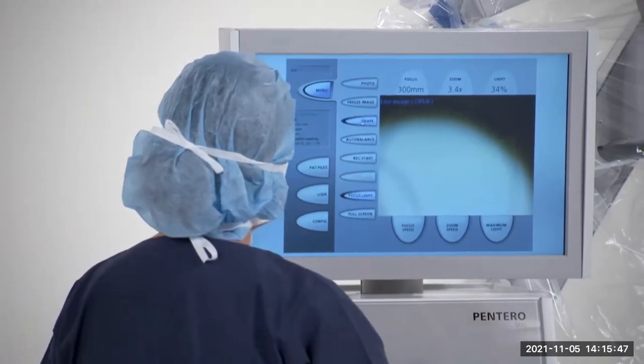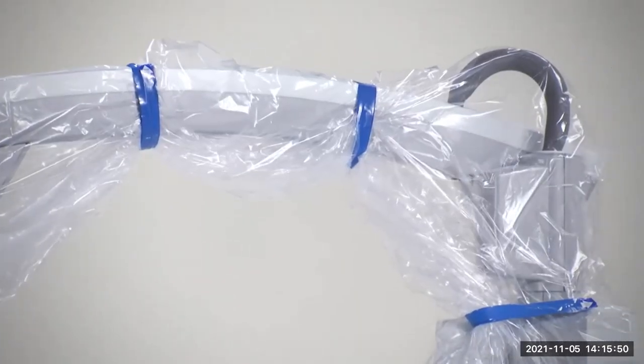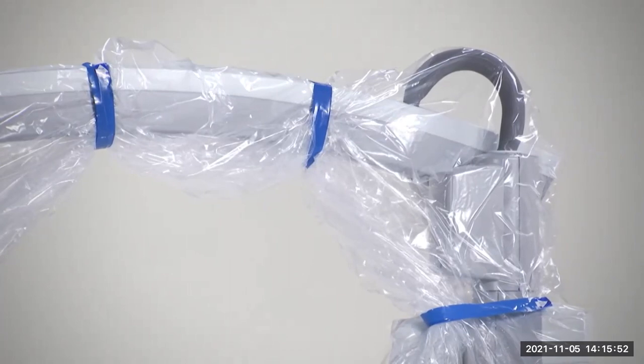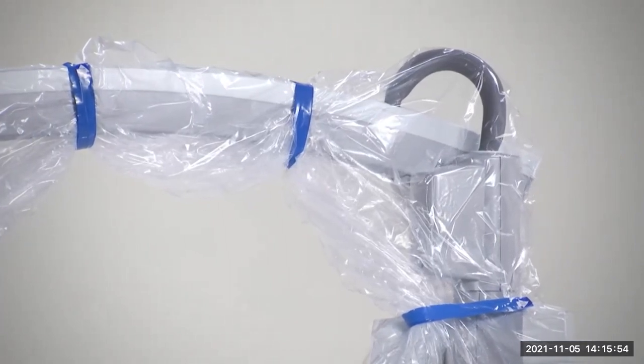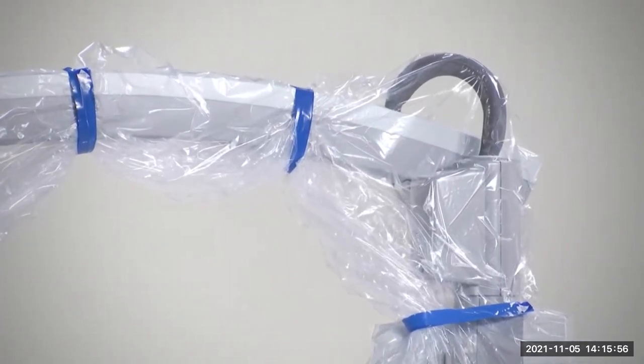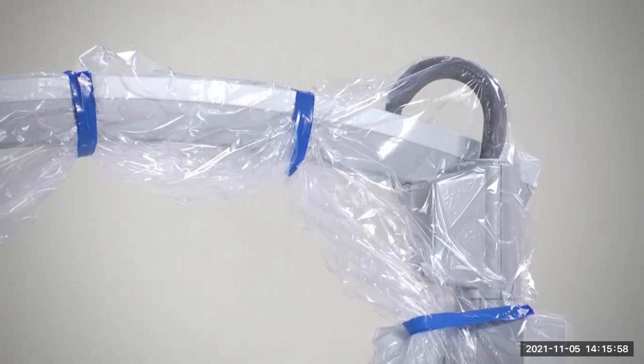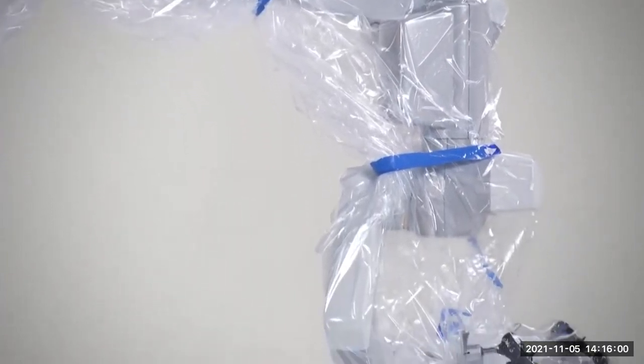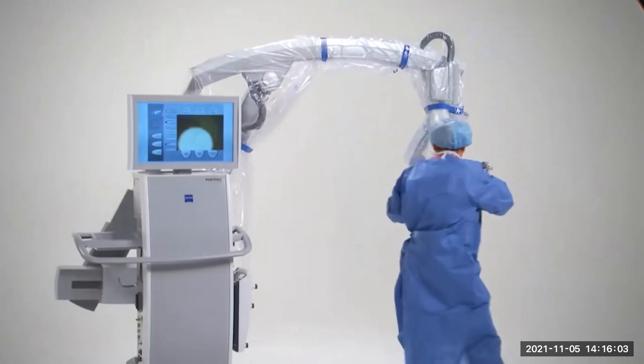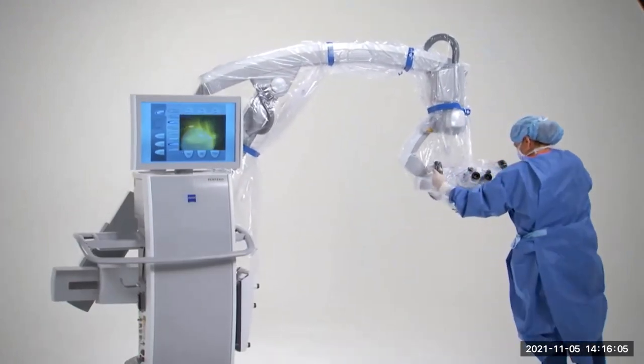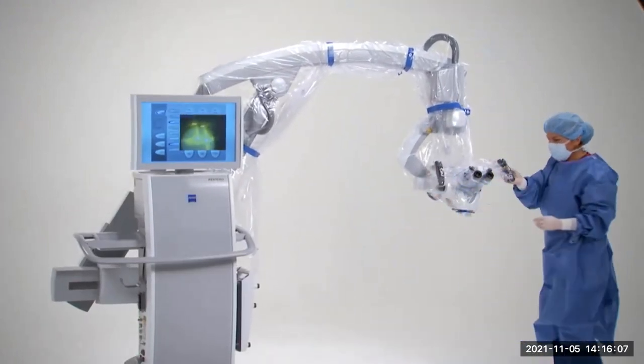If the microscope is equipped with auto drape, press the drape button in the main menu. This activates the pump. The pump system increases to maximum power for 2 minutes to extract the air from under the drape, and then switches to a lower speed to maintain air levels. Once the drape has been secured, check to ensure for ease of movement of all controls.